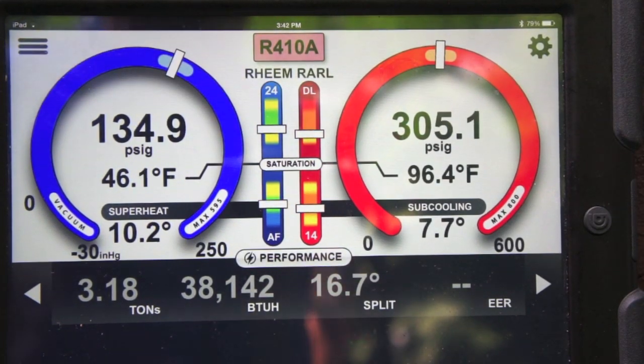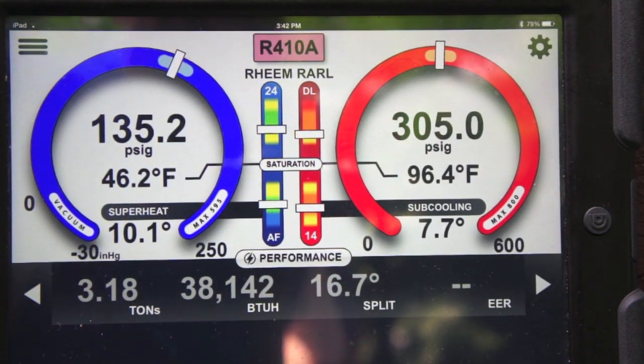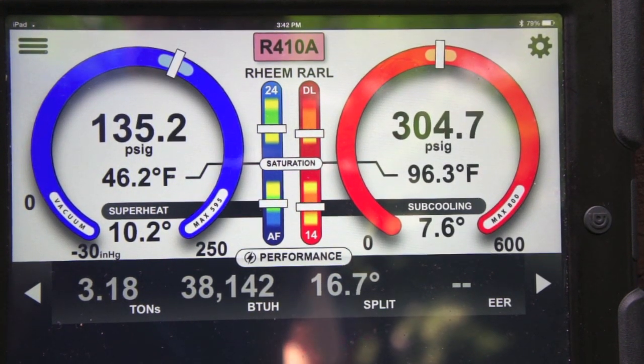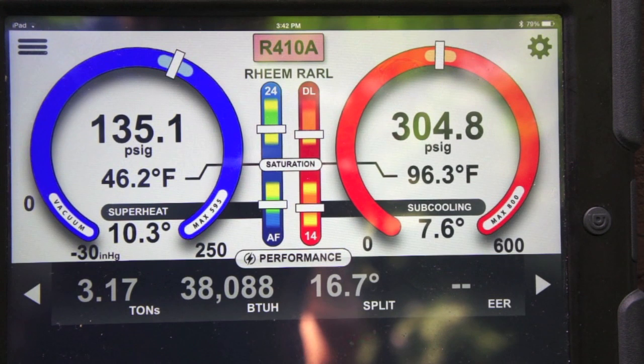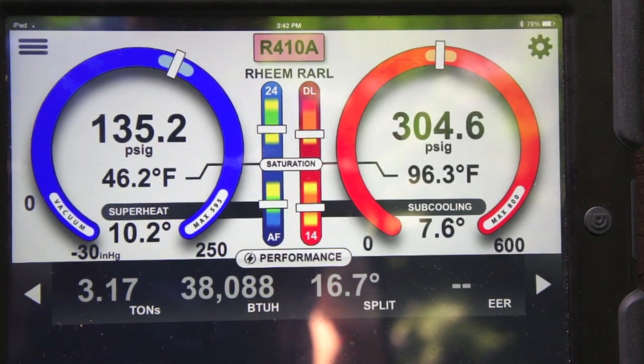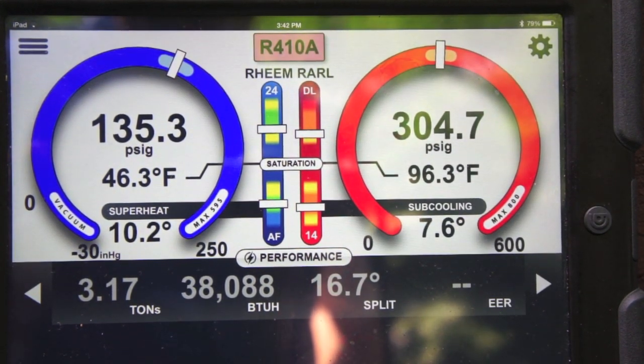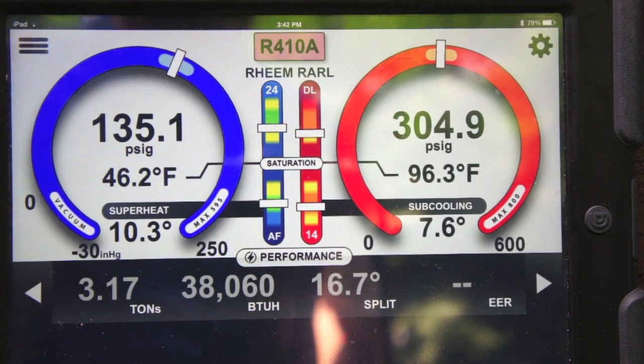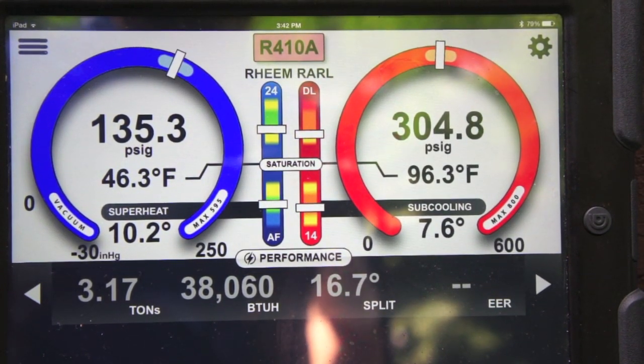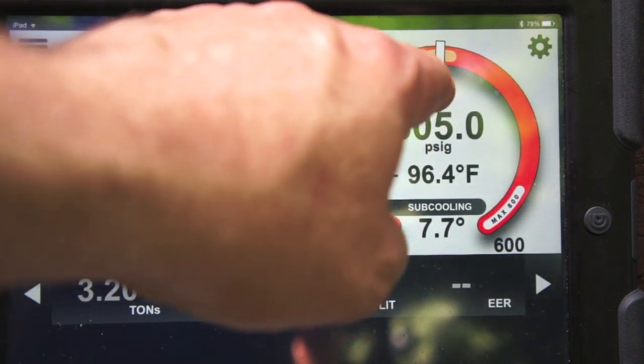Okay, we've got the unit running, everything's settled out now, system's profiled, and I just want to walk you through what we're looking at here and how this is going to work, because we're going to get ready to put in our electrical measurements. You need to let the system settle out and things get where they're supposed to be before you make your electrical measurements, because otherwise it's in a transitional phase. So you can see right now our suction pressure is right on, our head pressure is right on, subcooling is right in the center where it should be.